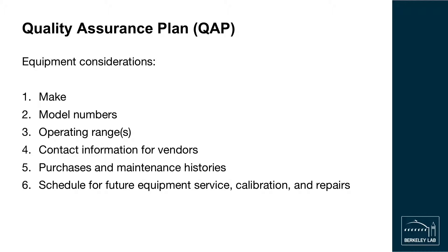When describing the equipment used in your laboratory, include make, model numbers, operating ranges, contact information for vendors, purchases and maintenance histories, and a schedule for future equipment service, calibration, and repairs. The quality assurance plan should be referenced and updated on a set schedule to ensure that all equipment is up to date on manufacturer recommended calibration.